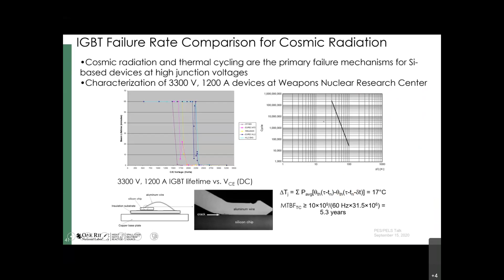We also looked at thermal cycling, and thermal cycling didn't look to be a problem. We're actually off the scale of this chart up above based upon our operating conditions. So that all looked pretty good. So what we recognized early on was that one of the problems was the voltage rating. We were running about 70-75% of the rating, which is almost unheard of, because we were using 3,300 volt devices and operating them up to about 2,400 volts of bus.